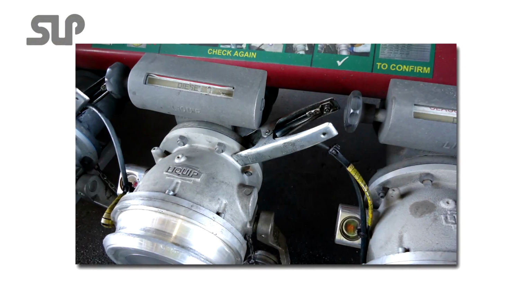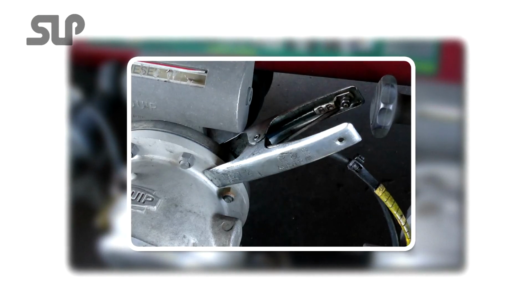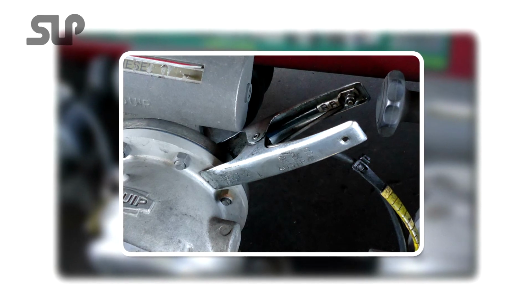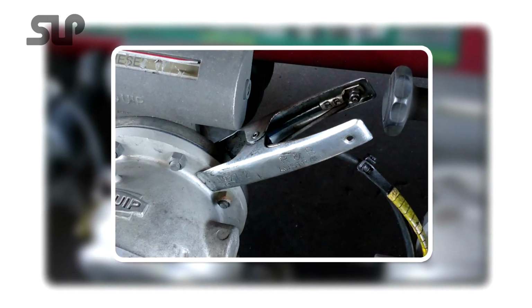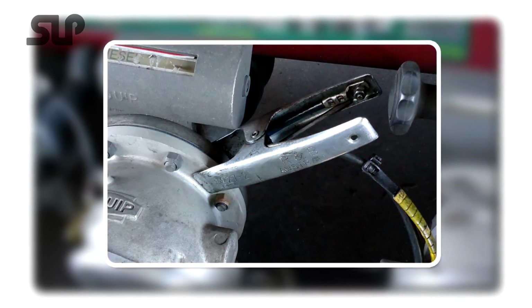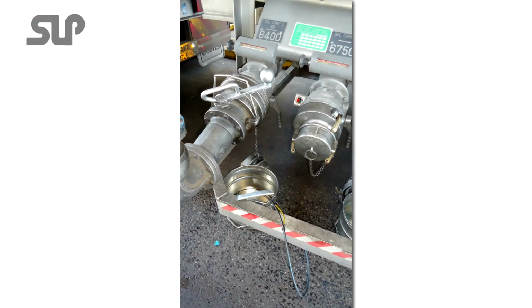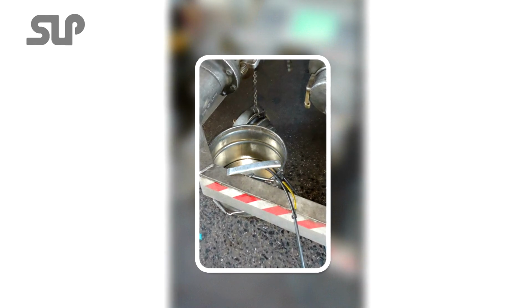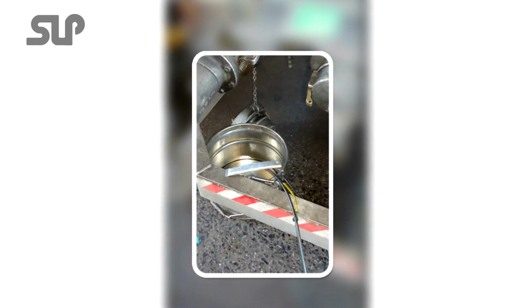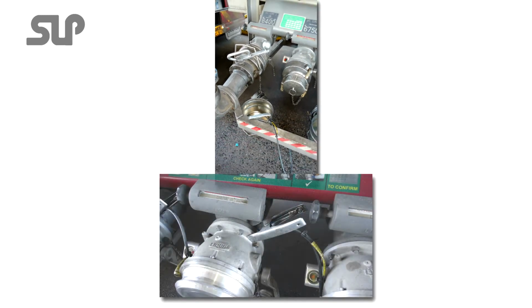Step 7. It is essential to ensure that all parts of the system, the tanker, the gantry, loading arms and containers for draining are static bonded at all times to minimize the buildup of static electricity and to assist with dispersing static electricity. Keeping all parts of the system bonded using static bonding cables ensures that they remain at the same electrical potential so that a spark cannot occur.